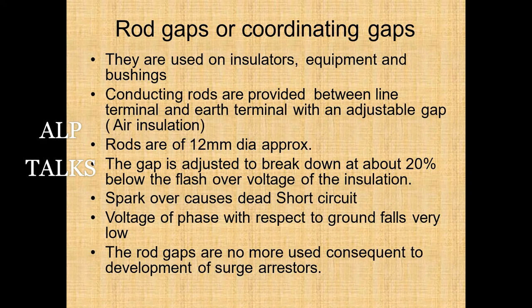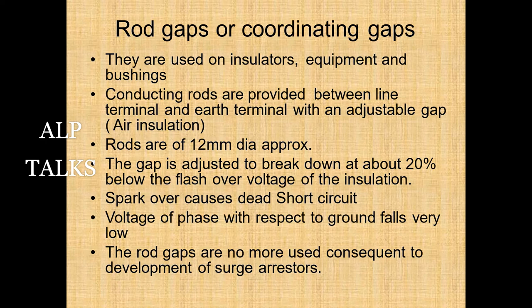Rod gaps or coordinating gaps are used on insulators, equipment, and bushings. Conducting rods are provided between the line terminal and earth terminal with an adjustable gap of approximately 12 mm diameter rods. The gap is adjusted to break down at about 20% below the flashover voltage of the insulation. Spark over causes a dead short circuit. Rod gaps are no longer commonly used following the development of surge arresters, though arcing horns on bushings may still be used as additional protection.